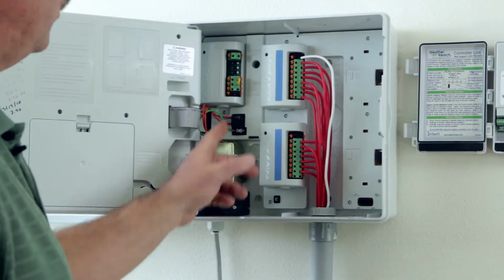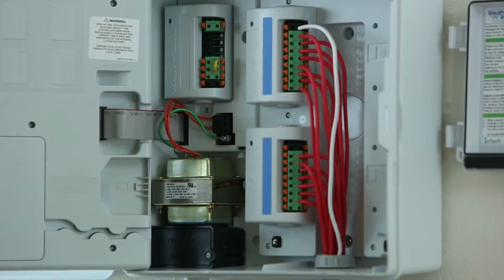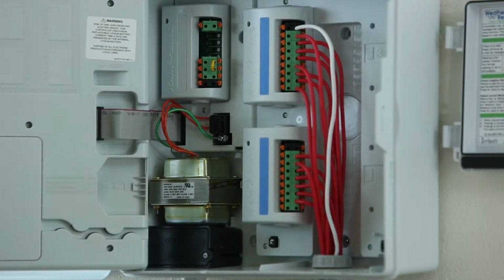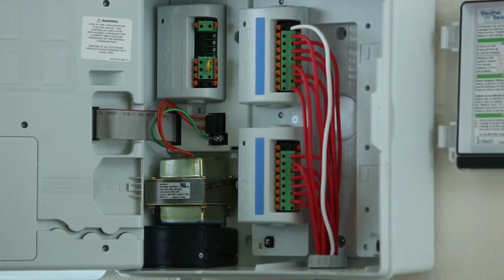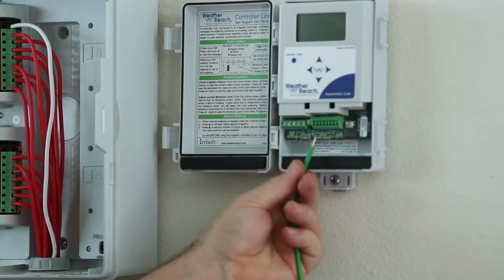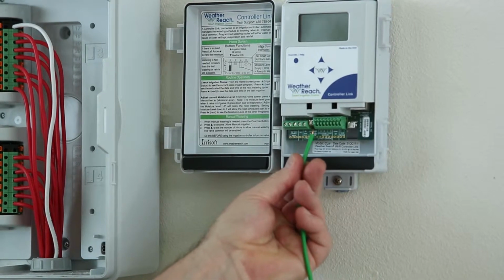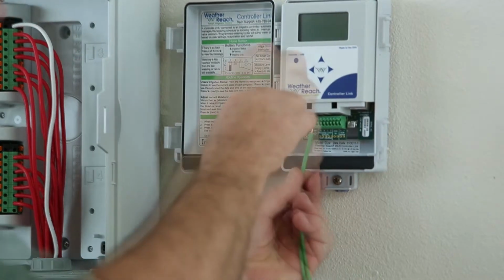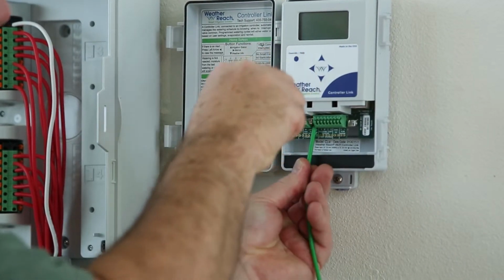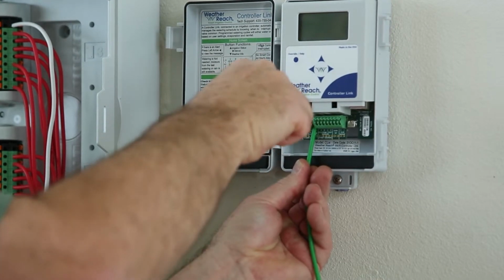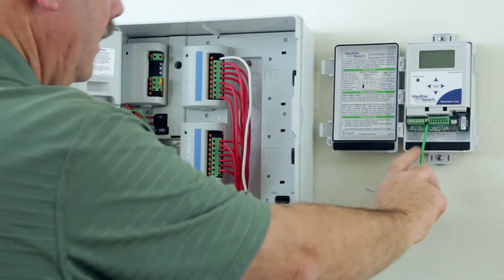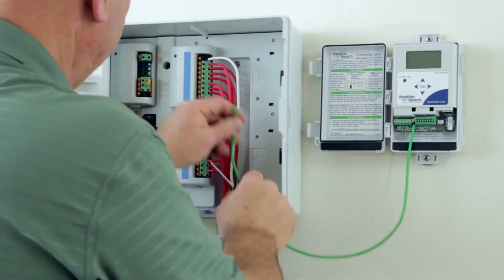The first connection should be to ground. Remember, proper grounding is essential for personal protection and enables surge protection. Connect a 12 or 14 gauge wire to the ground terminal. Then to earth ground.